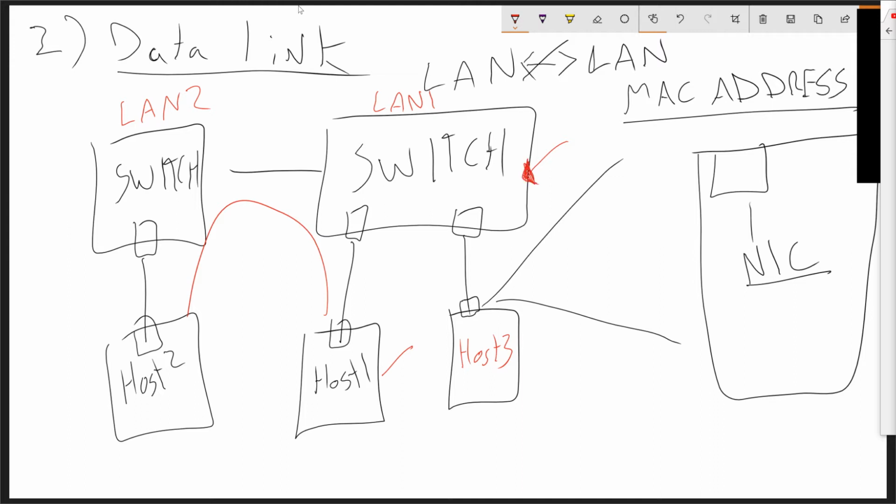I know a lot of folks make a big hoo-ha about getting Cisco certified as a BAS tech, but to be quite honest, on any medium to large size building or enterprise, they're not going to let you work on their networks anyways, so it's more important to understand the concept so that you can point the IT folks who are going to do the troubleshooting in the right direction. But as I said, if the IP settings were the same in host 1 and 3, you most likely have a data link issue.